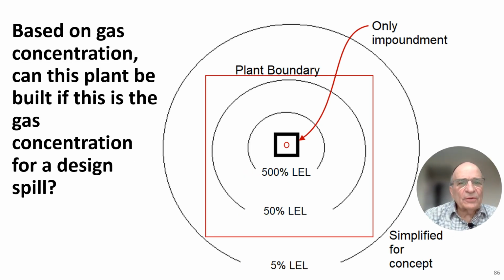So far, we've spoken about thermal radiation from fire. Now let's talk about gas concentration from a spill. Can this plant be built if this is the gas concentration for a design spill? If you look at it for a design spill, where is the 50% LEL level? It's right here within the boundary line. So yes, this plant can be built based on the design spill vapor concentration.